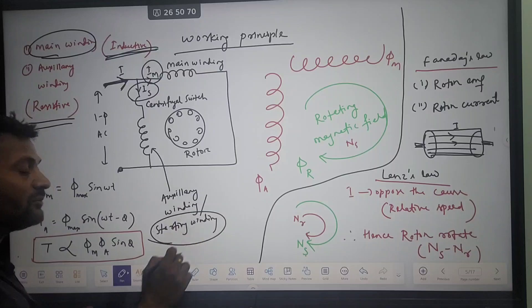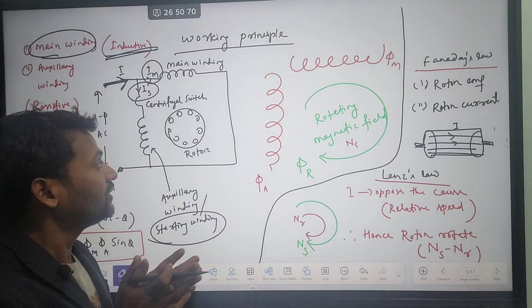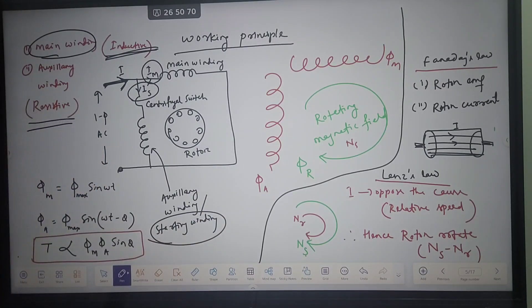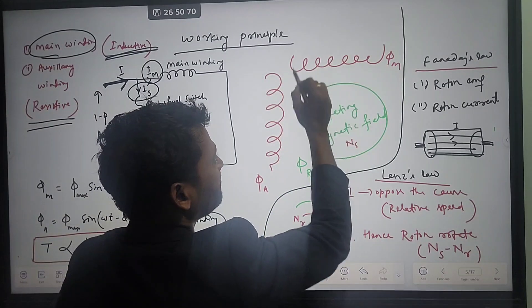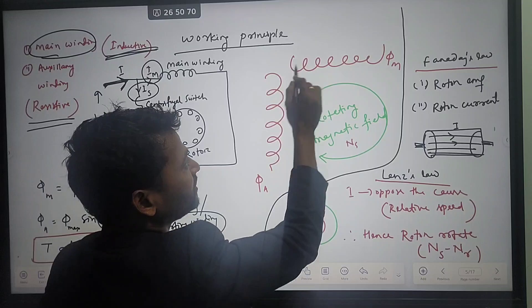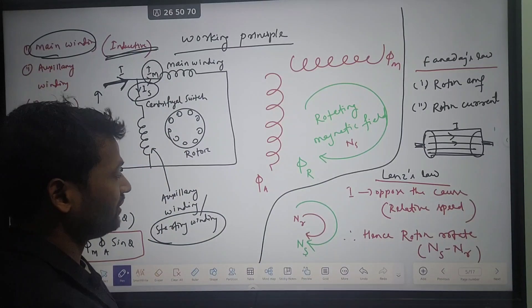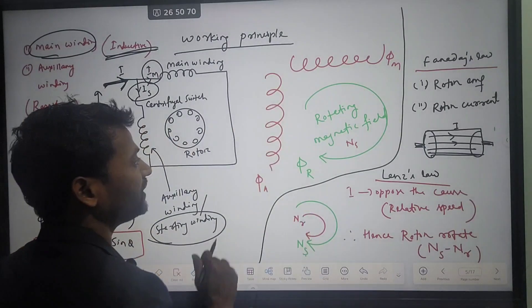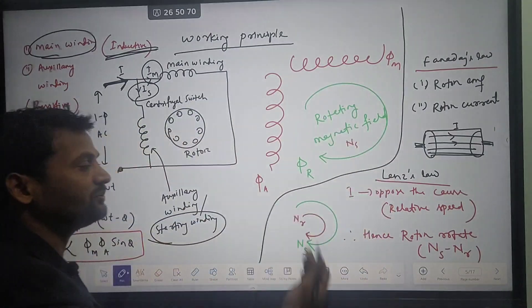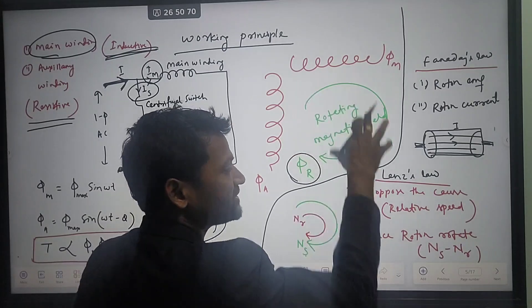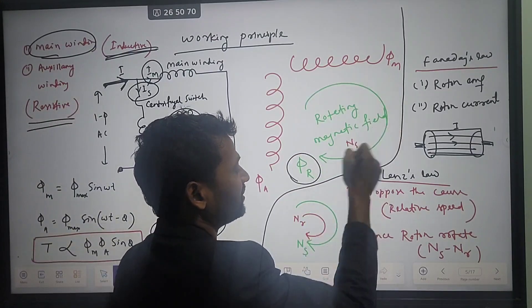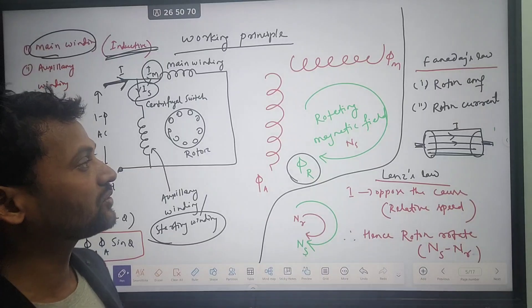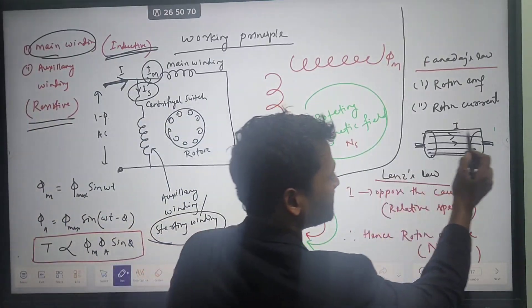The starting winding is used to split the phase — by using this winding we can make a revolving magnetic field. There are two windings: main winding and auxiliary winding, with 90 degrees between them. Due to the interaction between these two field windings, a rotating resultant magnetic field is developed. This imaginary magnetic field revolves. Now, if we keep a conductor inside this rotating magnetic field, as per Faraday's law of electromagnetic induction, an EMF will be induced.